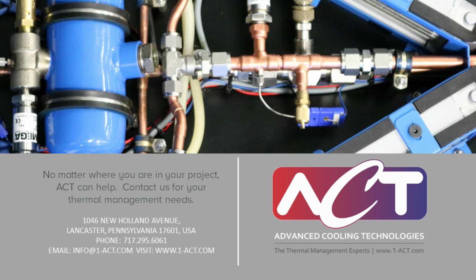In opportunities where you need a couple hundred cycles, we might recommend one of the organic blends that sustains its properties up through the low hundreds to high hundreds worth of cycles, and you start seeing some decay or degrading as those separate. And then there's some very pure, long chain hydrocarbons that are available in the market, and those will last you through tens of thousands of cycles without any noticeable degradation.